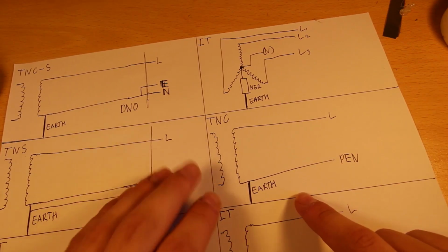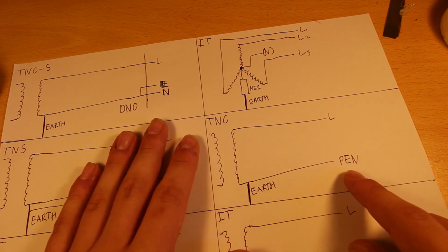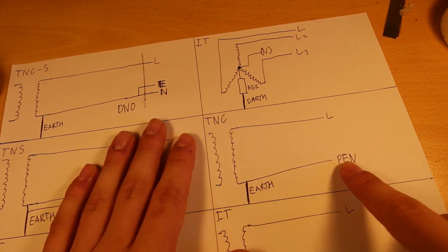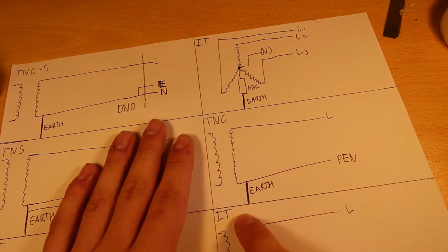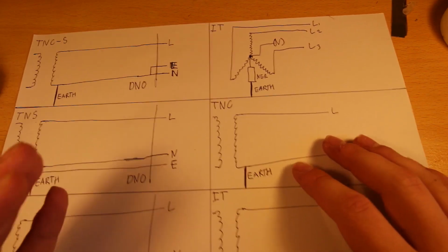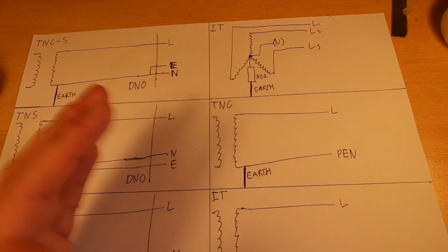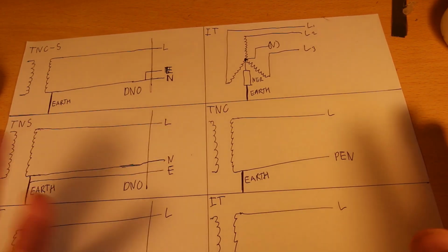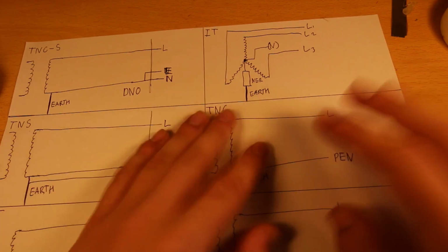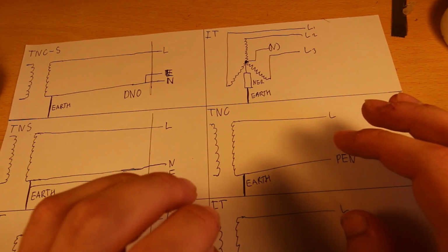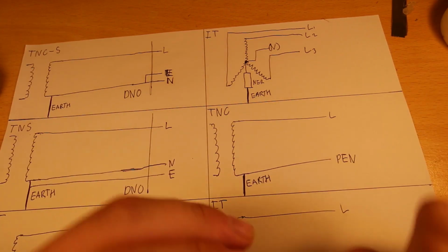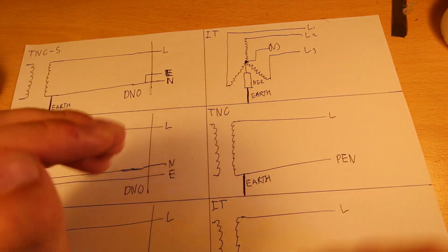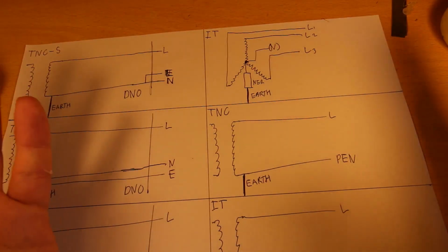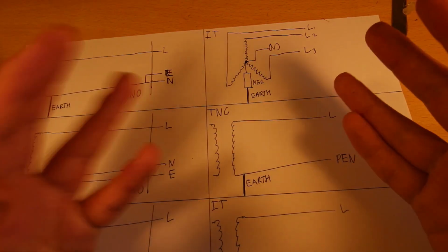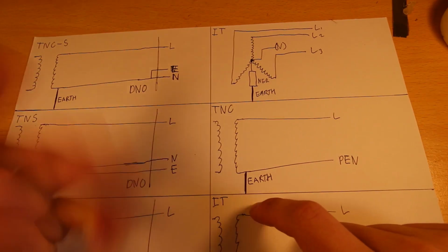We have TNC. TNC is for terra neutral connected. That is where you have the transformer, live, and then PEN rather than neutral because it's the protective earth neutral combined, which is earth referenced. There is a section in BS 7671 about this. I cannot think of any application where you would ever use it, because this falls under the Electricity Safety, Quality and Continuity Regulations or whatever it is, and in order to run a TNC system, I'm pretty sure you need a license from the Home Office, but it is in BS 7671, it is a thing that is mostly for distribution network operators though, or DNO. I should explain that.